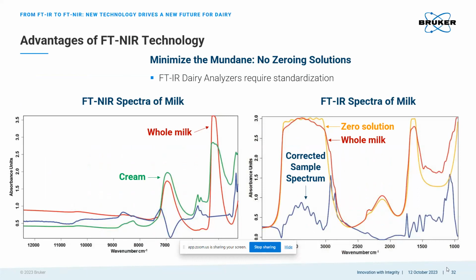There are also measurement conditions that we must take into consideration when comparing FT-IR and FT-NIR. So for FT-IR, pure water or zero solutions are measured to eliminate the interference fringes and to compensate for the spectral contribution of water. And we can see that in the right graph where our corrected sample spectrum is shown in blue. And these zero solutions are actually another source of potential error. And again, it's another aspect that does not have to be considered for our FT-NIR measurements.